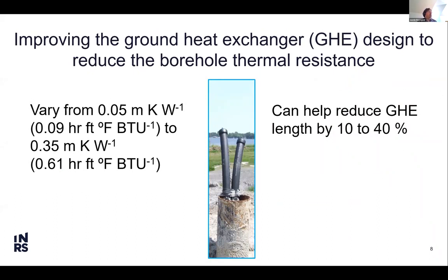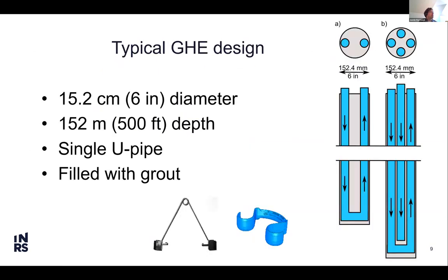So the idea to reduce the cost of ground heat exchangers is really to reduce borehole length. Typically, the thermal resistance of a ground heat exchanger varies from about 0.05 meters Kelvin per watt, which is a very small resistance, to 0.35 meters Kelvin per watt, which is a very high resistance. And by changing this, you have an effect on the length of the GHE. 40% would be a very large effect if you consider those kinds of resistance. But in a real system, it's always smaller than this. 0.05 is a fairly low number that we wish to achieve for efficient heat transfer.